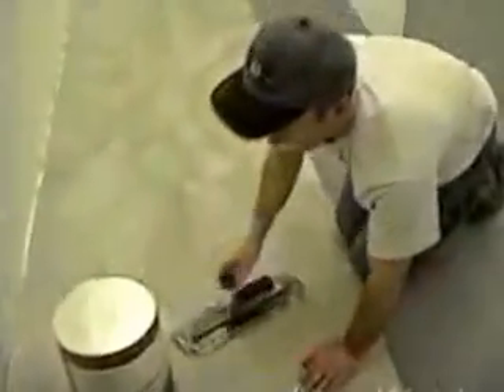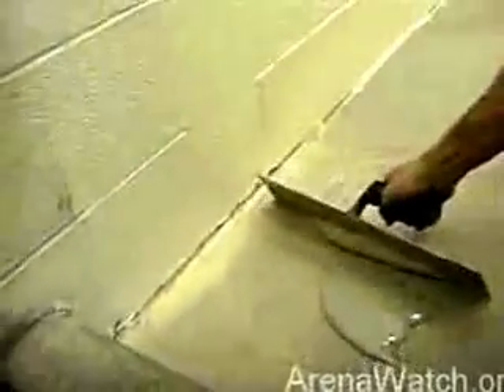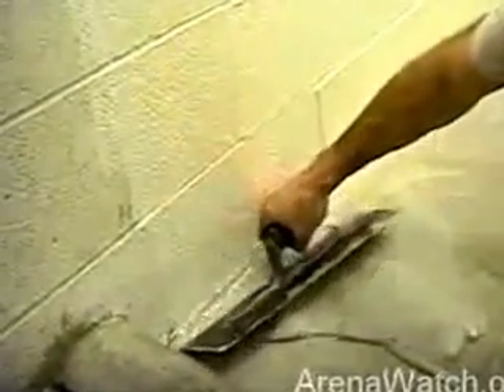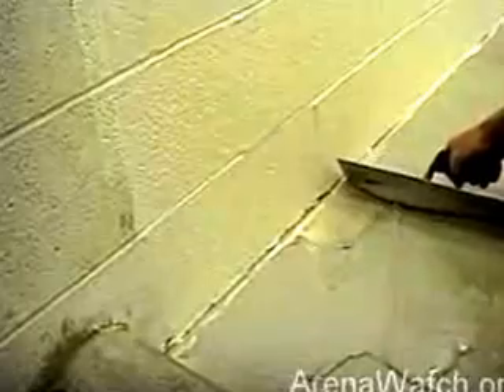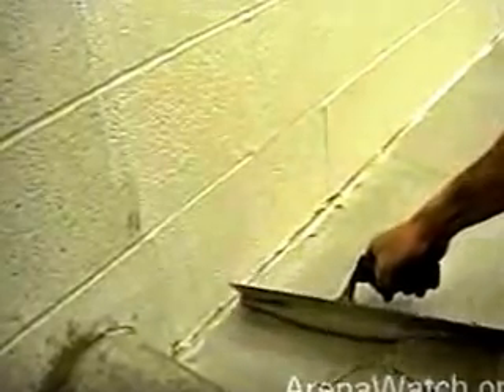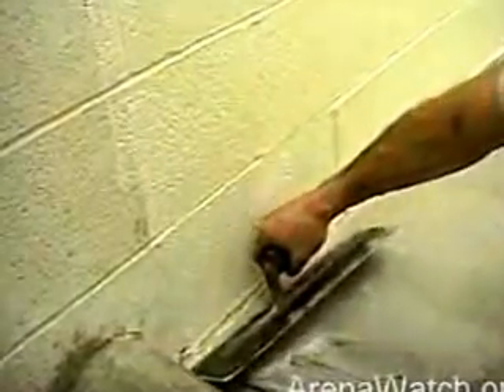One aspect we found with rubber flooring with masonry walls, which is pretty typical of an ice rink, is that the concrete work along the edge needs to be done very neatly and accurately, and this should be conveyed to the masons before they start on a building. The reason is that in a lot of rinks we don't put a cove base around the apex of the flooring to the wall, so to get a good quality joint with the rubber flooring, it's best the concrete's trimmed nice and neat, square on the edges, so they can just butt the rubber flooring to the wall without a lot of trim work or chip work on the concrete.